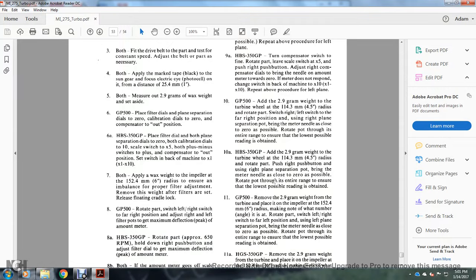GP500, add the 2.9 gram weight of the turbine wheel at 114.3 millimeter radius of the rotating part. Switch the right and left switch to the far right position using the right plane. And the separation pot, bring the meter needle the closest to the 0 possible and rotate the pot through the entire range. Ensure the lowest possible reading is obtained.